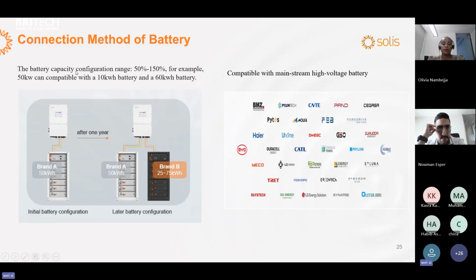For the battery capacity configuration range, we support this range. For example, if you have a 50 kWh battery, after 1 year with the load increasing, you may want to add another battery, and you can choose a different brand and different capacity. Then the system will still work normally. For the battery brand, we support this mainstream high voltage battery.